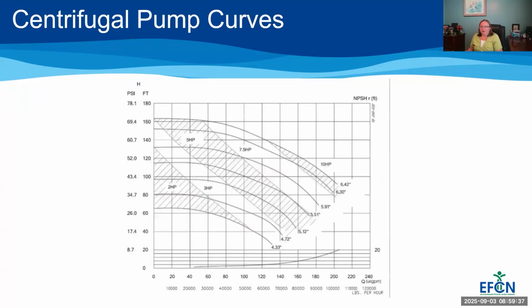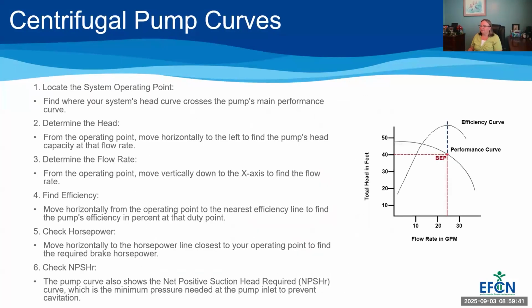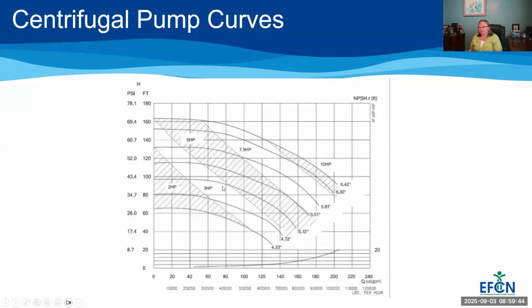And then the last thing about centrifugal pump curves, this one looked really clean and kind of easy to understand, but sometimes they look more like this. This is way more typical. And it can be really confusing, right? But what you're looking at here is head and flow rate, and then you're looking at different impeller diameters and different efficiencies. So understanding how to read a pump curve is important, just having a general idea of what's on a pump curve and why you would want to understand a pump curve, which is to allow you to select an efficient pump.